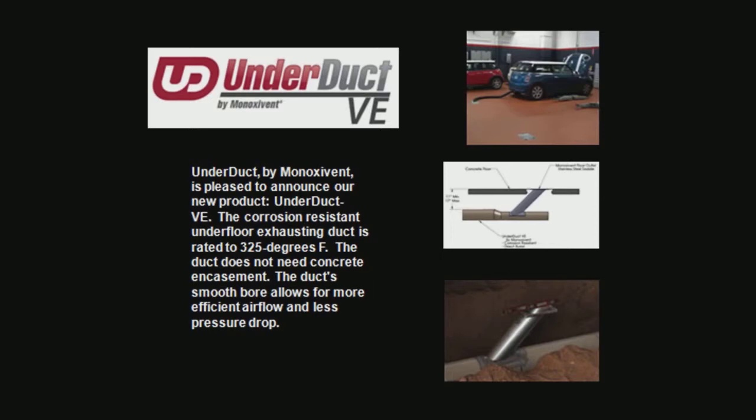It will not corrode. The problem with the standard ductwork is that eventually it will corrode and it can collapse. And if it collapses, it can then impede the airflow, and your system can end up being useless. And in order to replace it, you'd have to pull up all the concrete and dirt and then replace the ductwork. So we highly recommend that if you're designing an in-ground system, that you consider the VE Underduct FRP ductwork. It's a great asset to this type of a product offering.